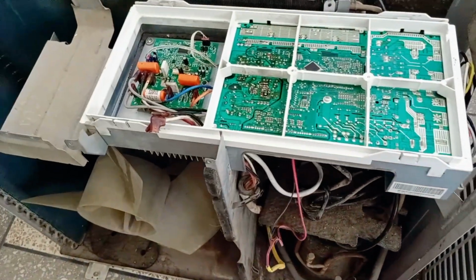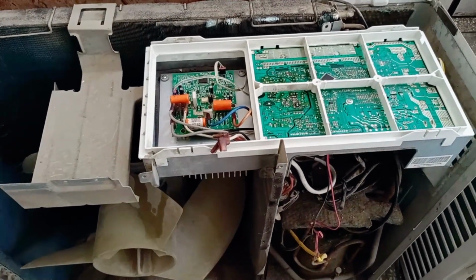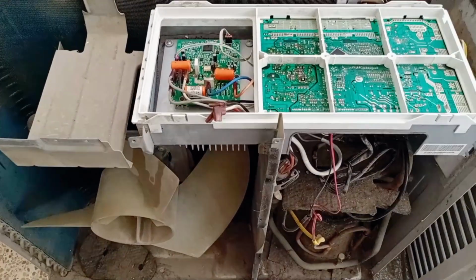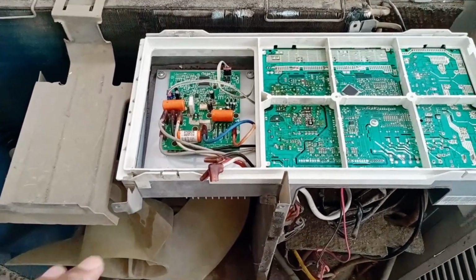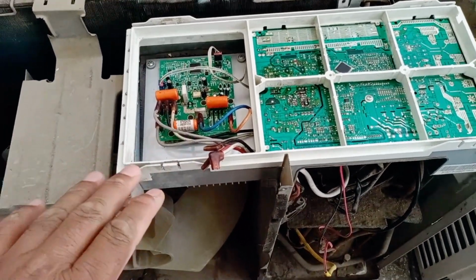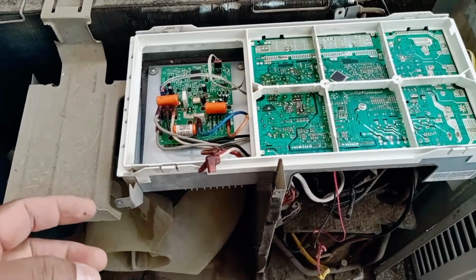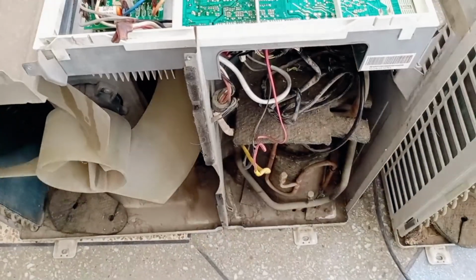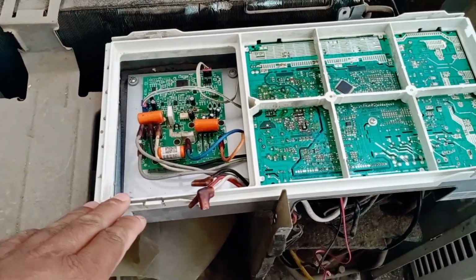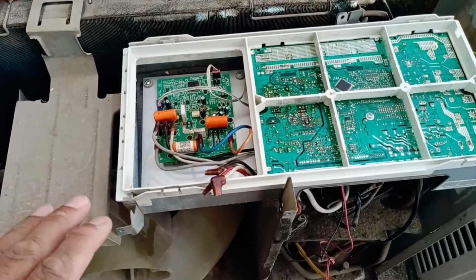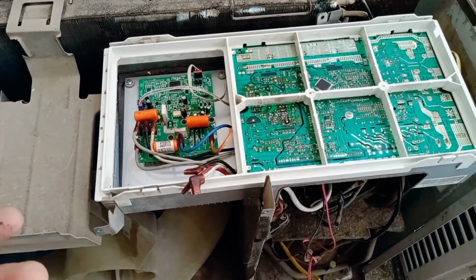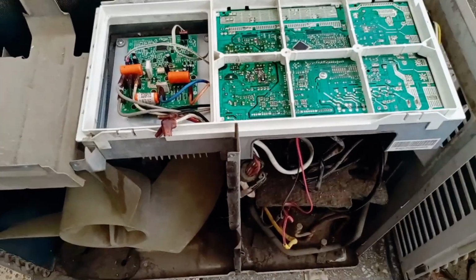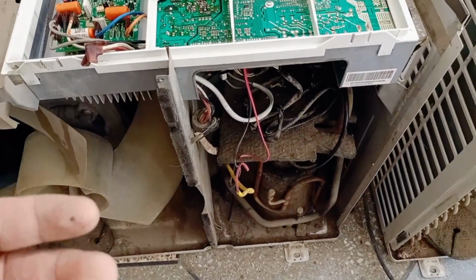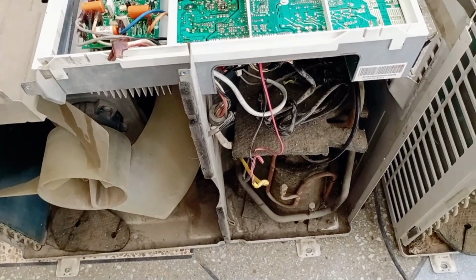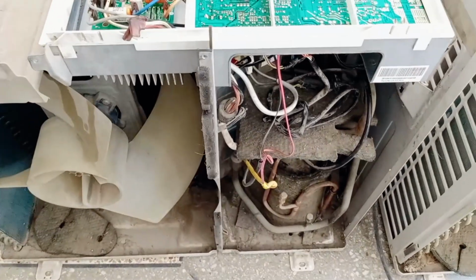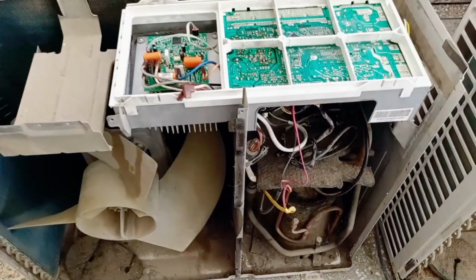The situation with the other unit is a bit different. Although the compressor in that unit is also faulty, what happens is that when I install the circuit board, the circuit behaves as if it's stuck or hanging. And what happens is that after leaving it for half an hour, it starts working again, but it doesn't function properly. The compressor in this unit is faulty in a different way, so this will give you some experience as well. If you encounter a compressor like this, don't connect a working circuit board to it either. Although the circuit board seems to recover, which is a bit strange, this usually doesn't happen and could instead damage something else in the circuit.